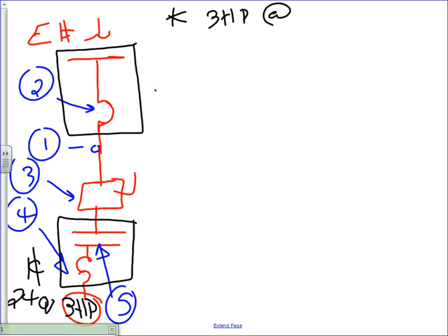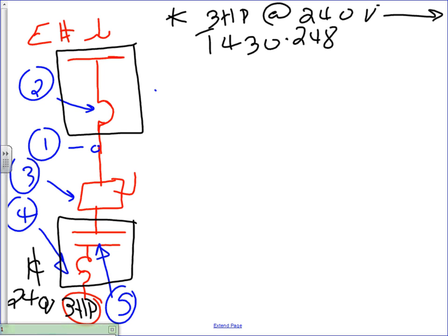at 240 volts. And if you take this one to table 430, table 430.248, thank you, table 248, you want to find a full load current. When it comes, guys, to sizing the conductors, we size everything based on something called full load current for motors. Full load current for motors.